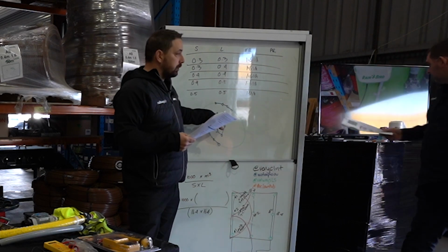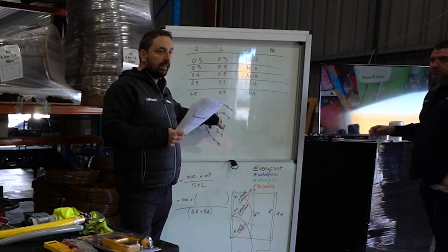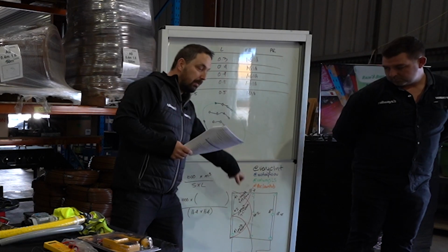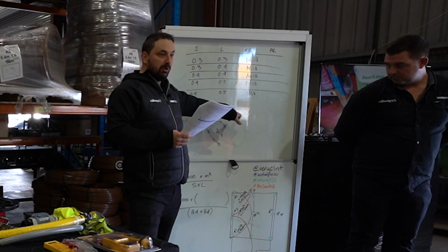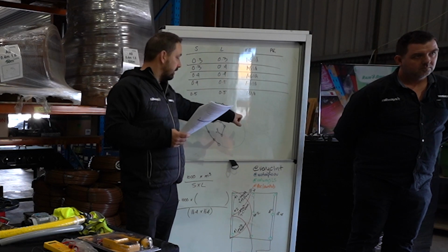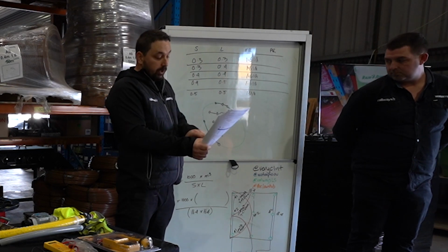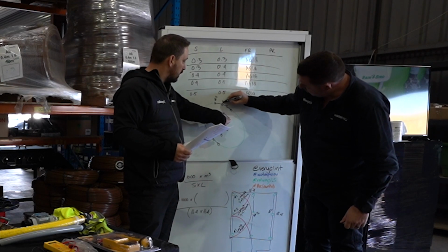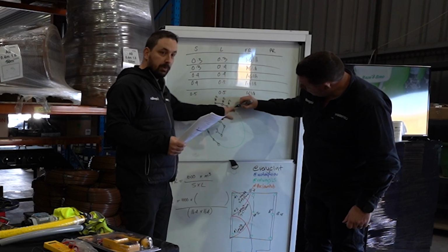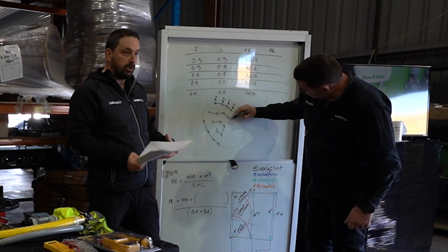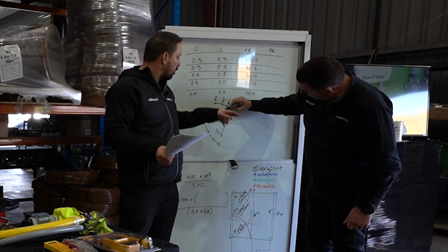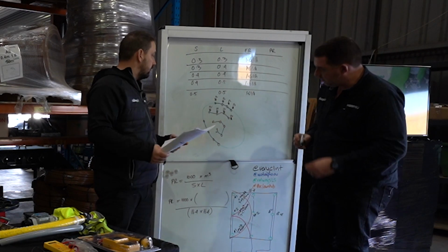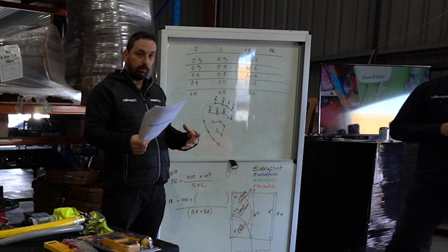So in this situation, where we combat that is we try and not do this by having all the same nozzle on one station. Like we said here, we're using a number 2 nozzle, for example. We might use all these as number 2s, but these half circles, because they're all half circles, we can also use those as all number 2s. All we have to do is run them for half the amount of runtime. And so then we're starting to impact our watering windows.